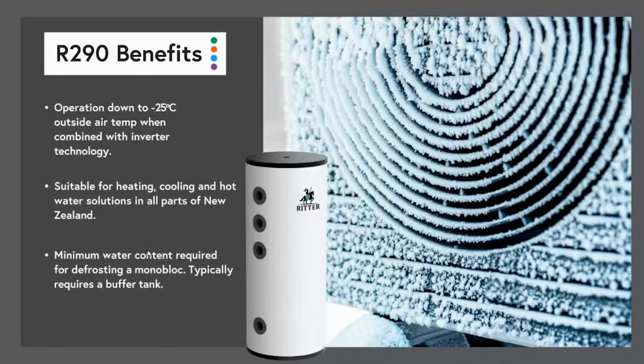Now, the last part of this slide talks about minimum water content. In this image, we're obviously looking at a pretty frosty heat pump. While this doesn't occur where I am here in Wellington, down in the South Island it can certainly occur on frosty mornings. So what is defrosting? A lot of people ask this. Every heat pump on the market has to do defrosting.